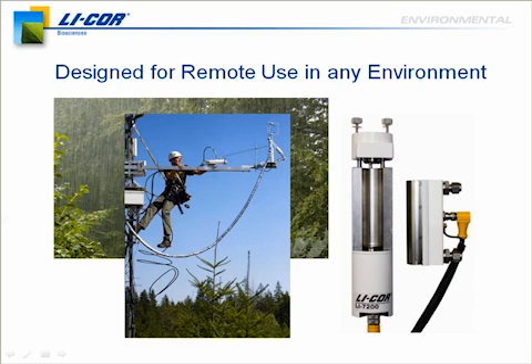And that's why we designed the 7200 to be so easy to use and so easy to clean in the field. It's got a straight path for the optics, so there's no bouncing, there's no mirrors. A lot of these newer laser-based instruments are going to have mirrors in them and high reflectivity cavities, and cleaning those can be extremely difficult, and keeping the reflectivity high enough to get good measurements. So having an instrument like this that you can just pull your shirt out, wipe it off, and put it back together, we think is going to make using the instrument in the field a lot easier.